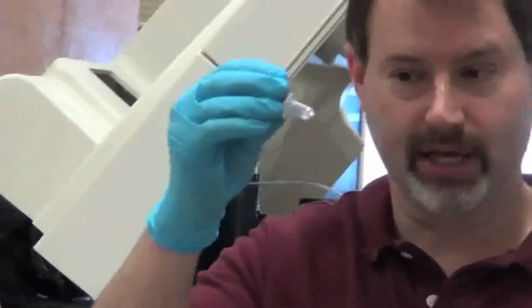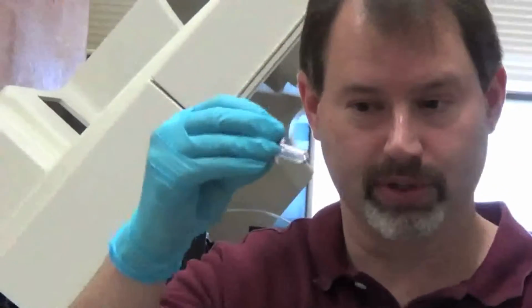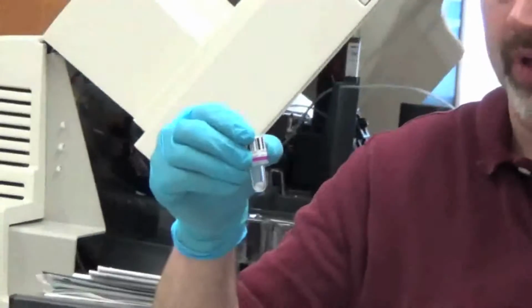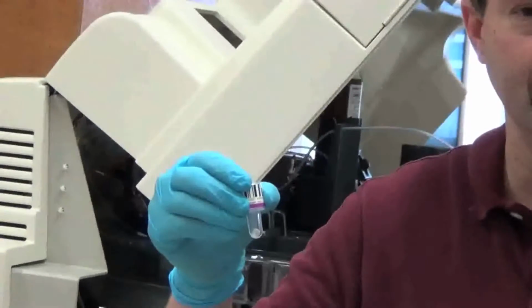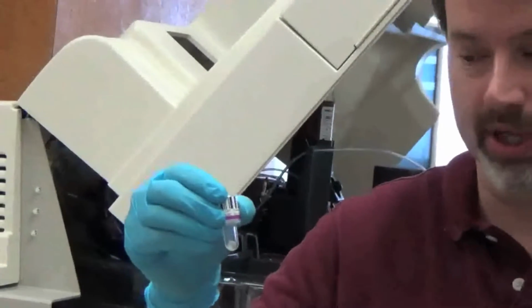Sample, we have to put a test tube in there, and this is a patented product from Siemens. In it, it has that little bead in the very bottom there, whether you can see that well or not, but it is a coated bead, and once it's put into the machine, it will remove the sample that's just ahead of it, as I just loaded there, and put it into here, and then start adding reagents on top of that. So it's a rather simple system, as long as we put the test tube right behind our sample tube, which has our serum in it.